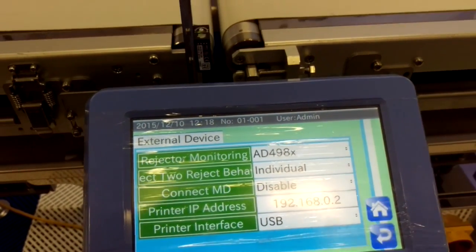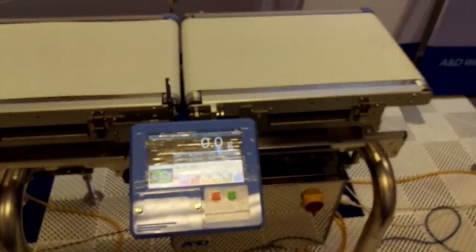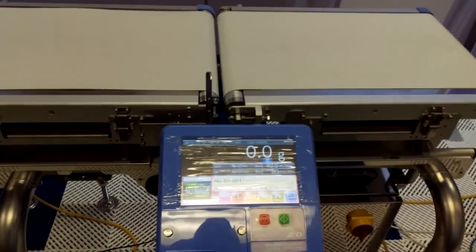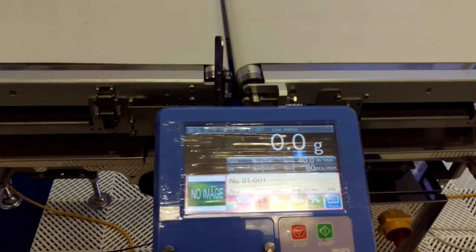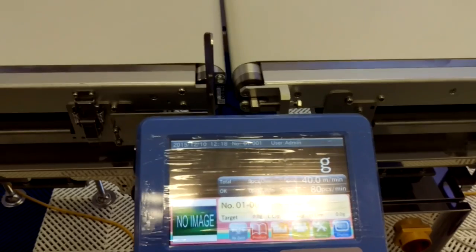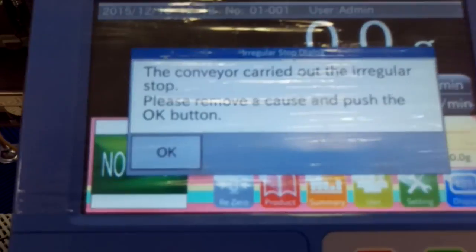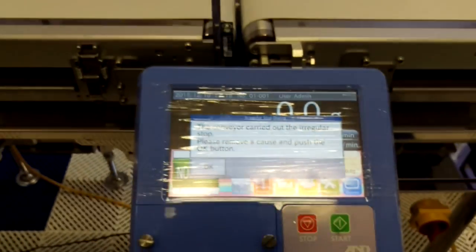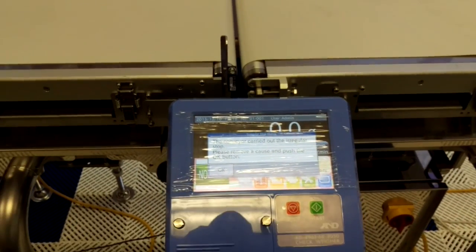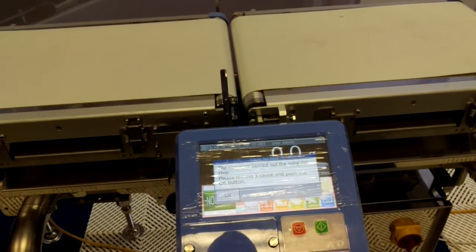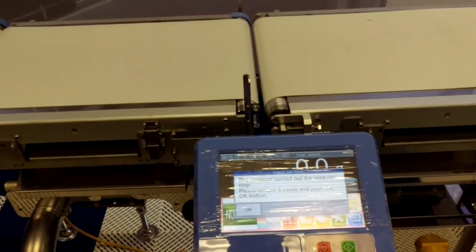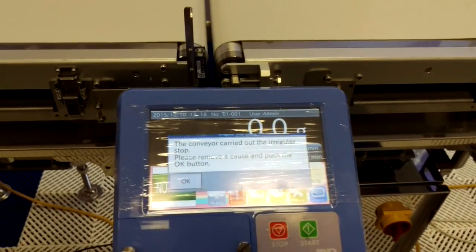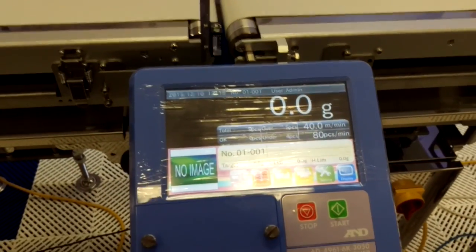Now what will happen when we start the checkweigher — and of course there's no reject connected to this one — so it's going to think there's an error straight away. As soon as you press start, it goes stop. There's a problem with the rejecter. The conveyor has a fault and the motor signal has come back to the checkweigher saying there's a problem, please fix it. So that's how you enable the reject monitoring.